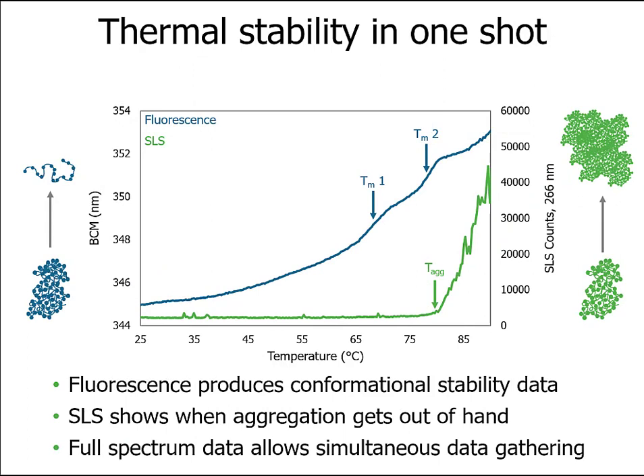UNCLE delivers on this fluorescence data simultaneously with gathering SLS data to get protein thermal stability and aggregation information in just a single experiment. Here we're looking at the results of a thermal ramp experiment where protein fluorescence is tracked in blue and SLS is in green. Fluorescence shows your proteins unfolding and quantifies that with melting temperatures at TM1 and TM2. The SLS data in green shows the aggregation behavior of your protein and reports the temperature when aggregation begins as Tagg. Notice how the Tagg event lines up with Tm2, linking the second unfolding event to aggregation of the protein.